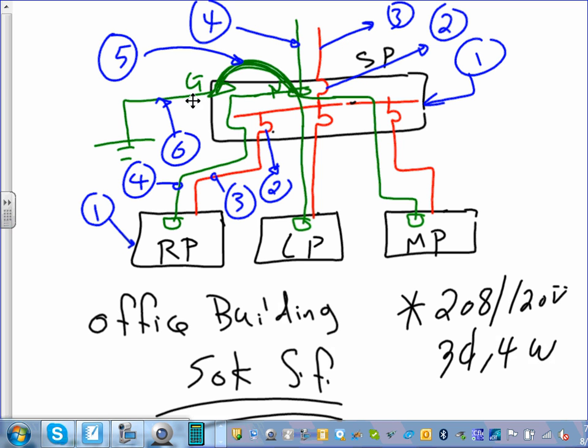Then number 6 is the wire that you take from the ground bar inside the panel. There's a bar. That's a ground bar. You take it and you bond it to the ground rod. That's number 6. This guy here is the symbol for the ground. Then we're going to go down. That's a service. Right underneath it, guys, the feeders. Can you guys see these 3 feeders coming to 3 panels? We talked about feeders versus service: service at the top, feeders at the bottom. All these feeders, you guys are going to size the following. Number 1, you need to size the panel itself. That's all. How many panels do we need to size here? 3 panels: RP, LP, and MP, receptacle, light, and mechanical.